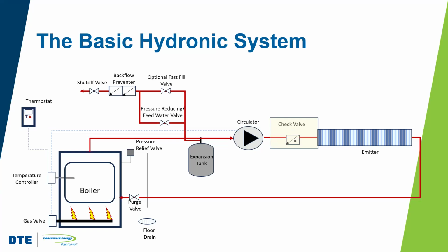Thermal siphoning. This happens because of the difference in density between the cold return water and the hot water supply. Right, so because of that difference in density, you may get what we call thermal siphoning, where the heat may drift when the boiler is not functioning. The heat may drift over into the emitters, and so we're going to stop that. We've got a check valve that stops that hot water from flowing, right? Because that's an undesirable situation. There are times when we do design thermal siphoning into systems, but in this particular case, it's not something that we want to have happening here. So we're going to have a valve there to prevent it.